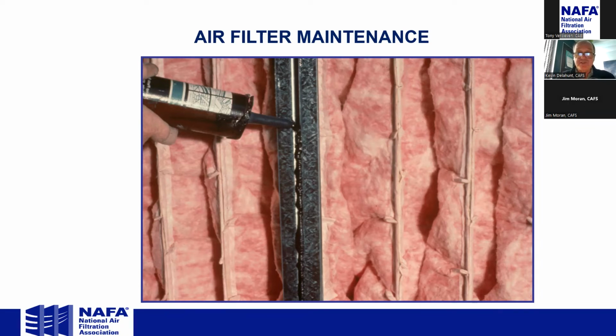It's very difficult to get a positive seal between two pieces of metal. So we suggest that even caulking the filters, or making sure you have some gasket between the filters, is a good preventive measure to, again, try to make sure that all the air is going through the filters.